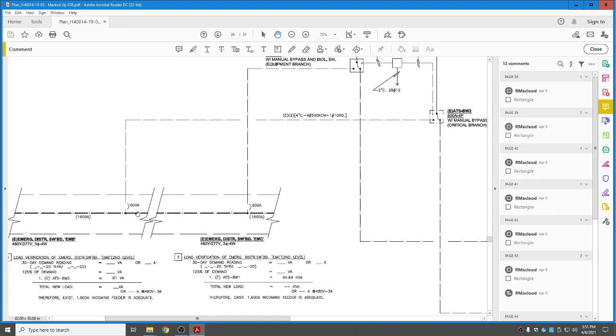from the emergency generator, we're providing power off of emergency distribution switchboard EMB. It comes up with what looks like two 4-inch conduits with 4 number 500 KCM size cables plus one number 1 ground that will connect to this ATS. So we have normal power here and we have E-power. We're typically running on the normal power, but in the event of a loss of normal power, this leg trips over, completes the circuit, and then we start drawing power off our generators.